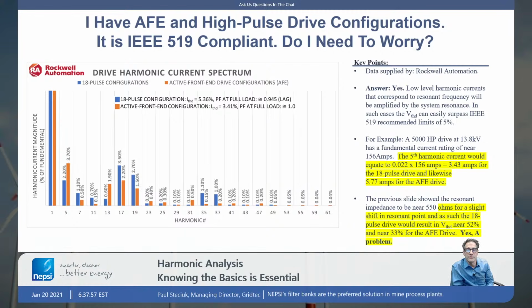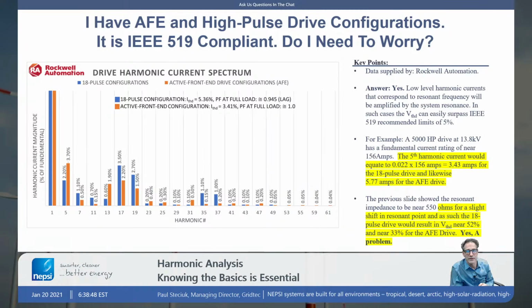The one thing that we often see is that nowadays there are what are called active front-end drives or high pulse drives where the harmonic currents are low. And in the United States, they would say that, well, that's an IEEE 519 compliant drive. It complies with the standard. If it complies with the standard, then I don't need to worry about harmonics. That's what's talked about. So I took some Rockwell Automation drive data, and I said, okay, in this situation, if I were to have a 5,000 horsepower drive and I were to connect it to this network, I would have a certain amount of harmonic current times that impedance, and I would get a distortion value that would still be excessive. And you can do the same for both types of drives here.